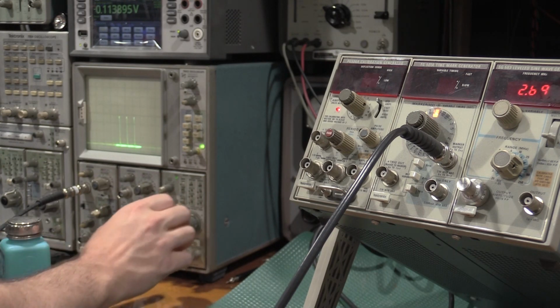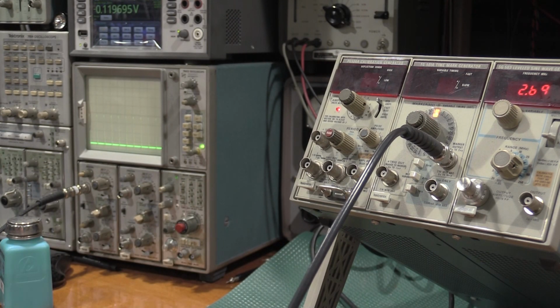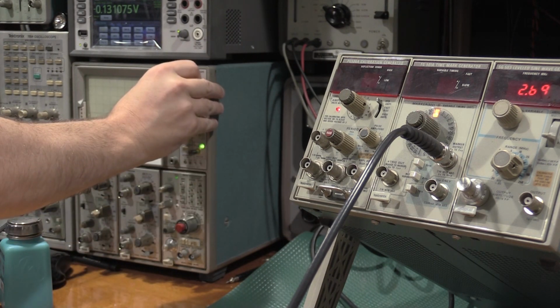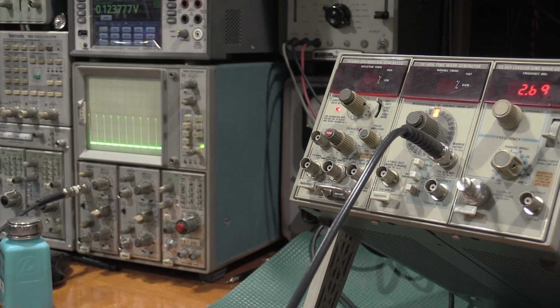waveforms. Okay, I was telling the scope to sweep at 0.1 milliseconds, and I had the time mark generator set at 0.1 seconds, so the trigger was just out to lunch because it was running way too slowly. As we can see, we get nice time marks. We can check the frequency real quick.